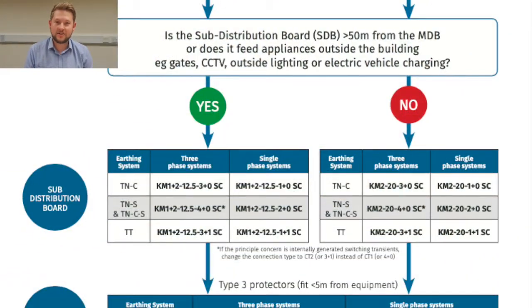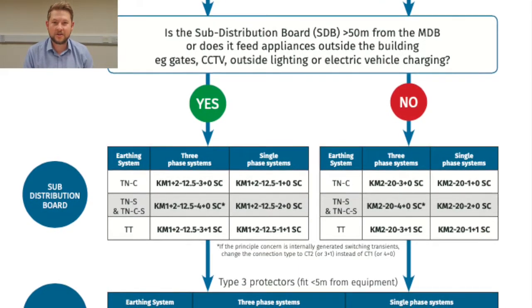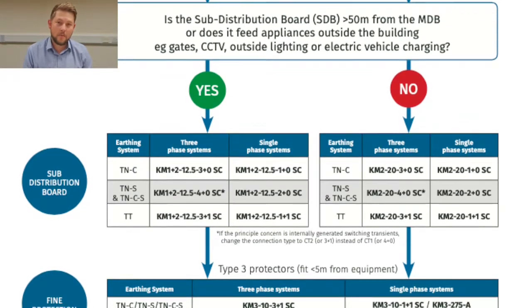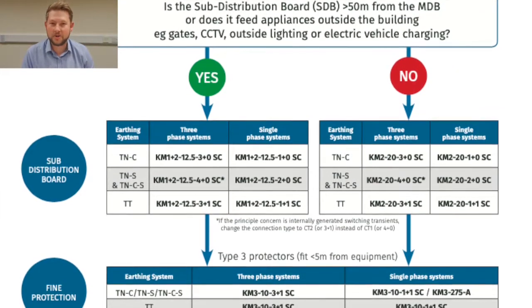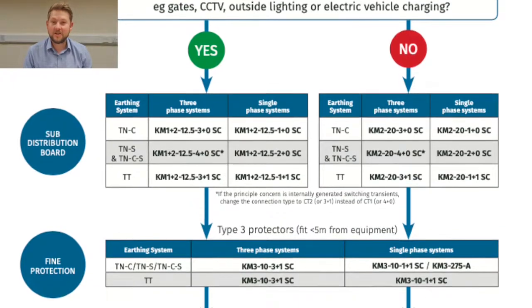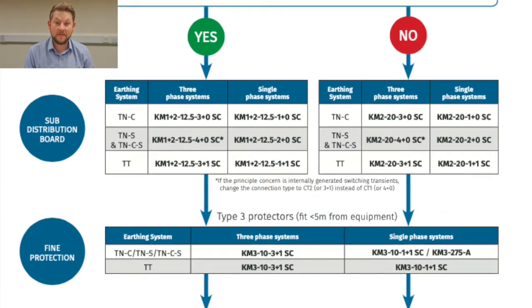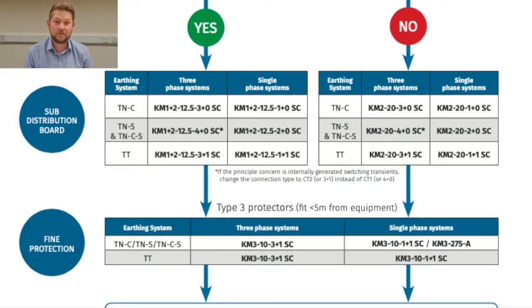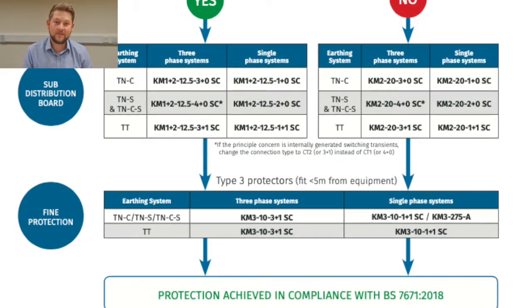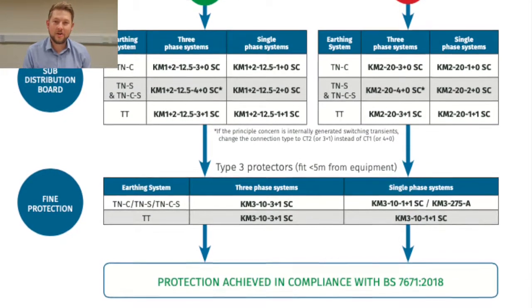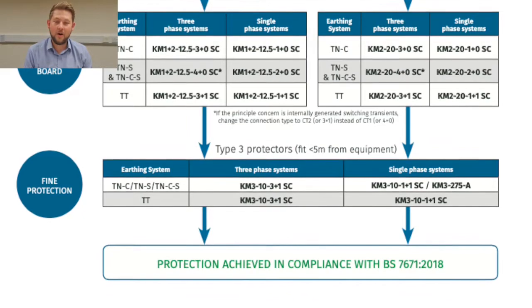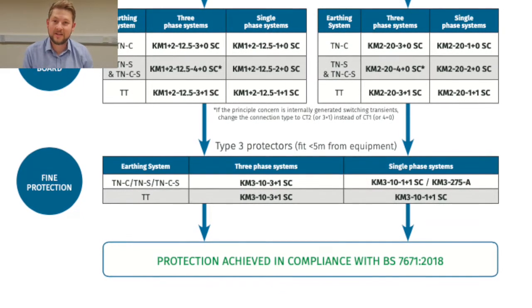The final consideration is fine protection, or type 3 devices. Type 3 devices are typically installed within 5 meters of the terminal equipment — meaning anything from servers to computers, or anything of particular importance or value that we're looking to protect. These devices are very simple to select; we only need to know the phase, whether it's three phase or single phase. We have two types: one is DIN rail mountable, a modular device, and the second is a three-wire connection which can be installed inside trunking, within ceilings, or anywhere else where a DIN rail mountable device isn't suitable.